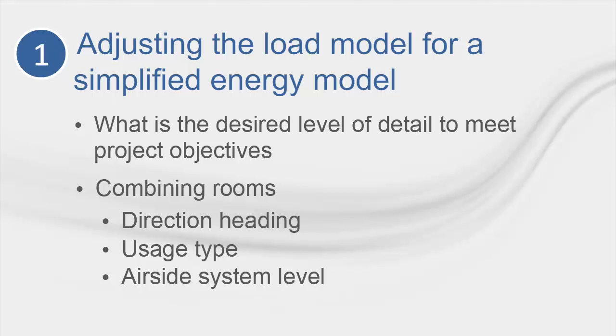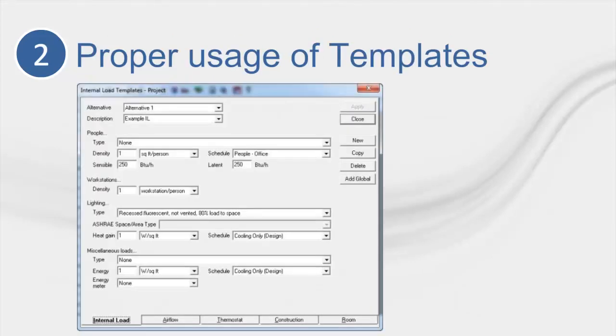To continue, when zoning a model for energy analysis, you must also include already designed HVAC systems. Make sure to take into account the as-designed zoning model, as this will dictate which rooms can be zoned together. Finally, the benefit of simplifying the model commonly manifests by limiting the opportunity for mistakes, reducing the potential for unmet hours, and significantly reducing calculation time.